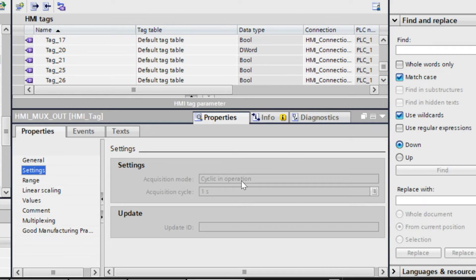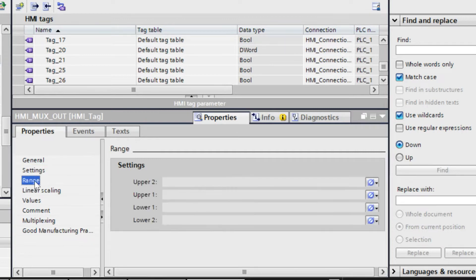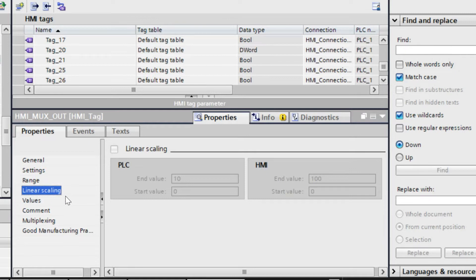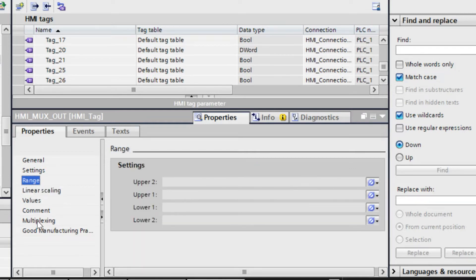Here you can also see the settings. If you take a tag from the PLC, you can see the cyclic operation — the interval at which you want to update data from the PLC to the HMI. You can select seconds, milliseconds, minutes, or hours. In the range section you can give a range for your input. There is also linear scaling, which we already talked about.